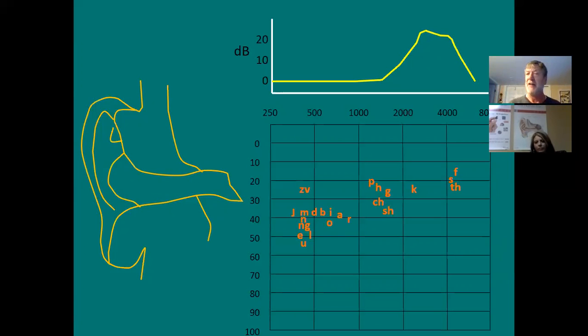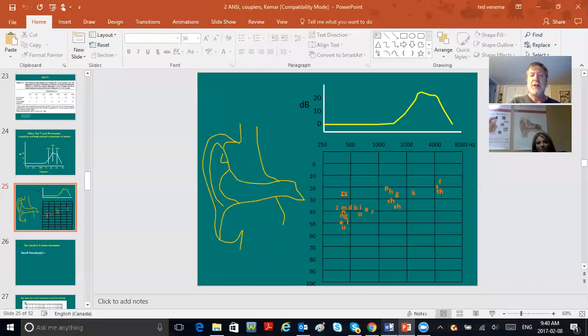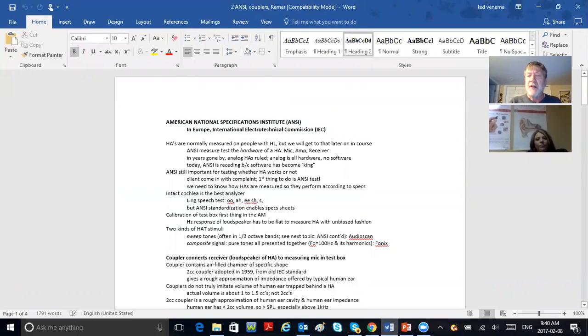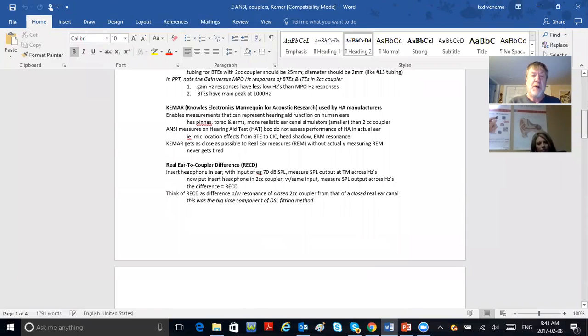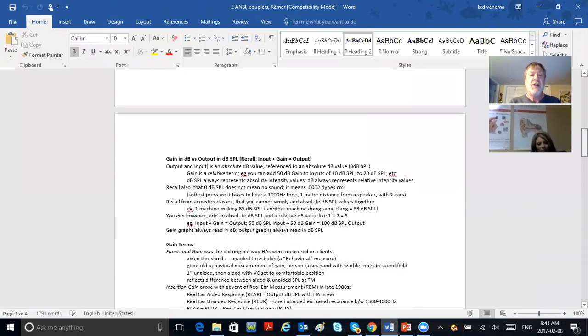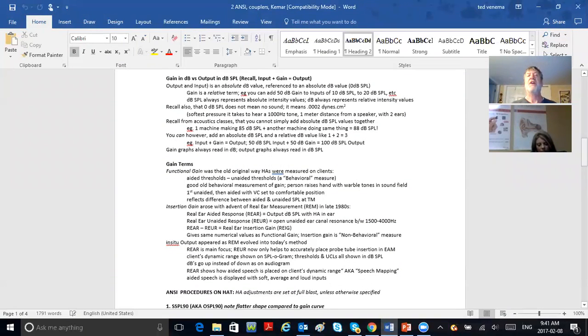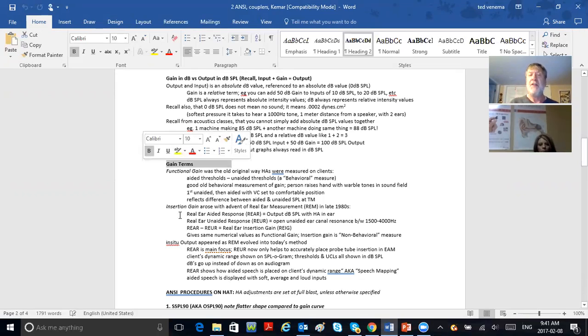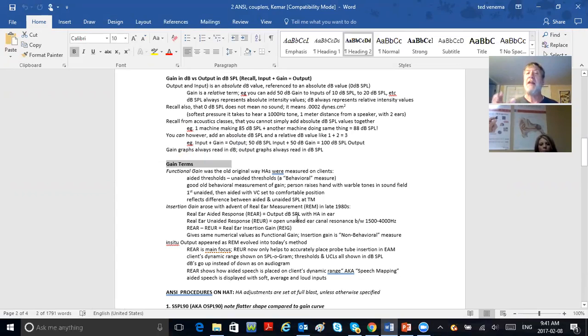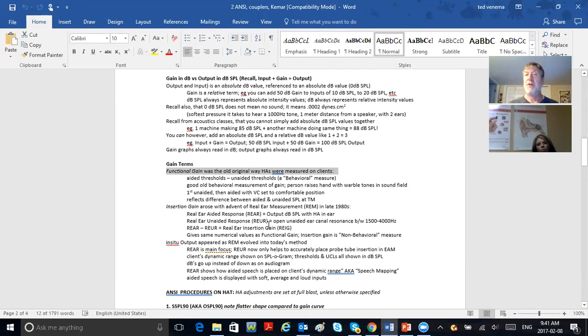Now let's look at where we are in the notes. We talked about KEMAR, real ear to coupler difference, gain in dB versus output in dB SPL—very important to always keep that in mind. Then we talked about gain terms. The way hearing aid fittings used to be done before real ear was called functional gain: you took thresholds under headphones, put the person in a sound booth with a hearing aid in one ear, plugged the other, and the person listened to warble tones from a speaker.